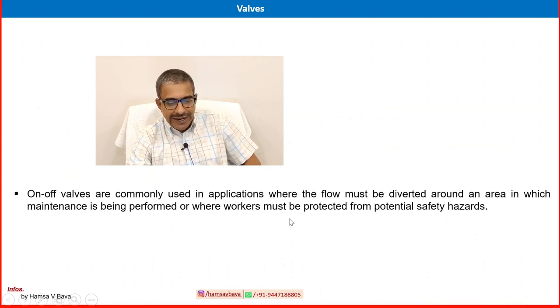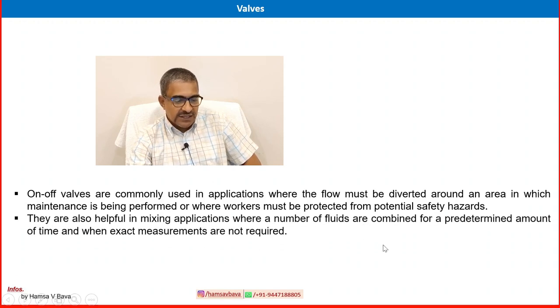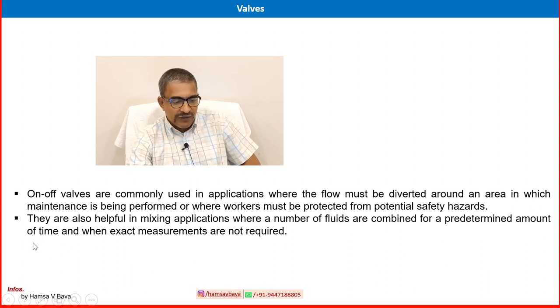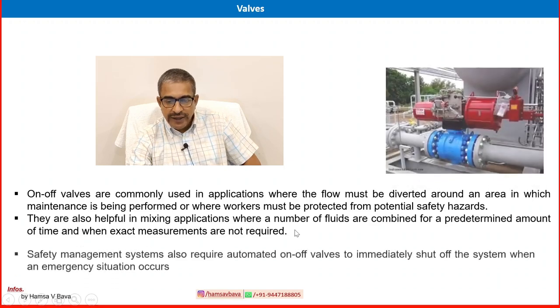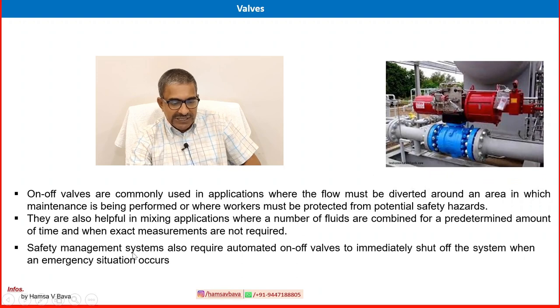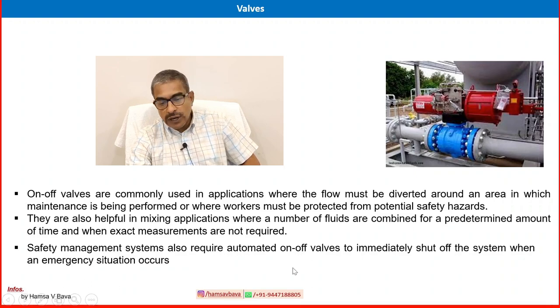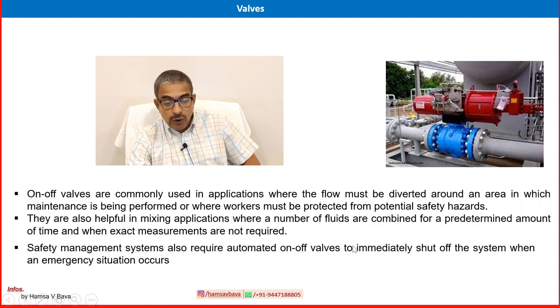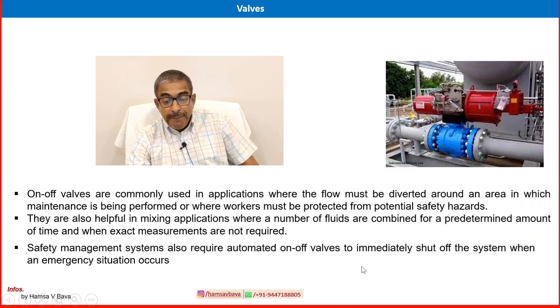On-off valves are commonly used in applications where flow must be diverted around an area in which maintenance is being performed, or where workers must be protected from potential safety hazards. They are also useful in mixing applications where fluids are combined for a predetermined amount of time and exact measures are not required. Safety management systems also require automated on-off valves to immediately shut off the system when an emergency occurs — that valve is called an SDV, or shutdown valve. It is automated using air, electrical, or hydraulic signals.